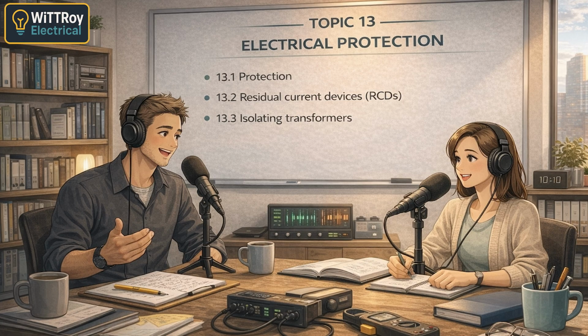Why do we use them? For extra safety. Correct. Higher personal protection, like in childcare centres or special locations. Yes. Now, what is the maximum rated residual current for a 10 milliamp RCD? 10 milliamps. Correct. And how fast must it trip at rated current? 40 milliseconds. Yes. And at 5 times rated current? Also 40 milliseconds. Correct.